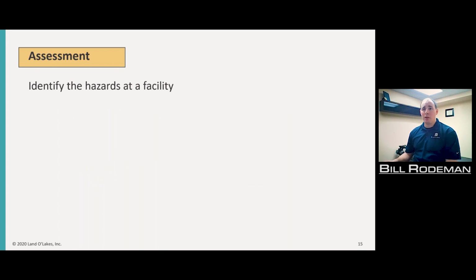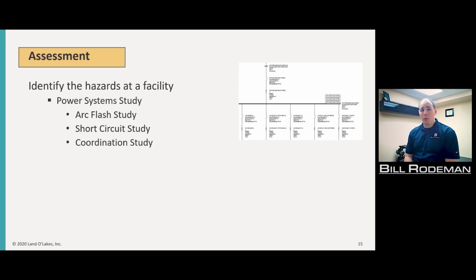Looking at assessment, identifying the hazards at a facility. One of the best ways to identify the initial hazards is to do a power system study. This is often referred to as an arc flash study or an incident energy analysis, but that's really only one part of it. I have 3 elements listed here: the arc flash study, short circuit study, and coordination study, but there are so many other elements that can be incorporated here, like motor transients, load flow, equipment evaluation, everything like that. There's a lot of different elements you can look at, but these are really 3 of the main ones.